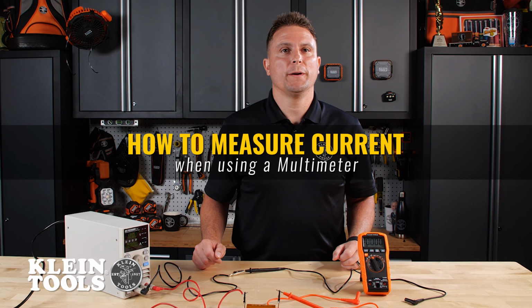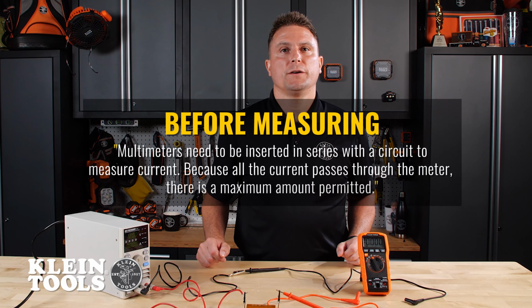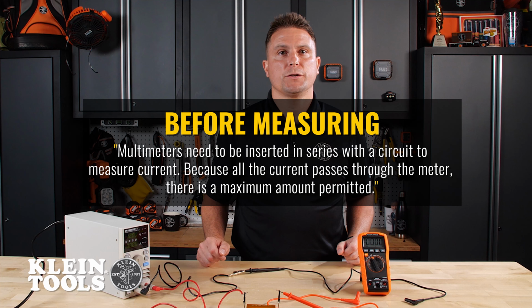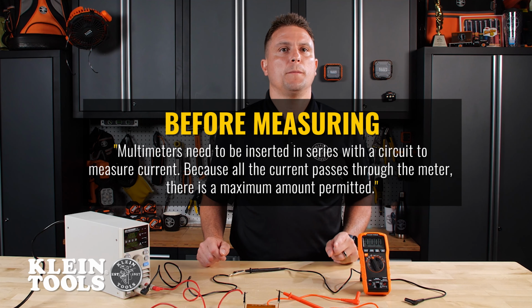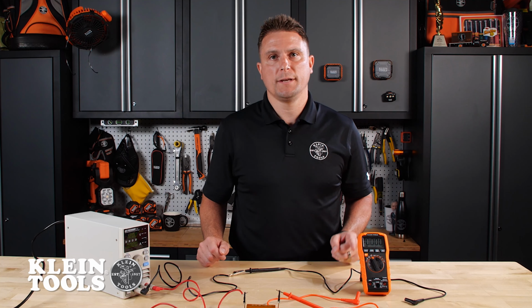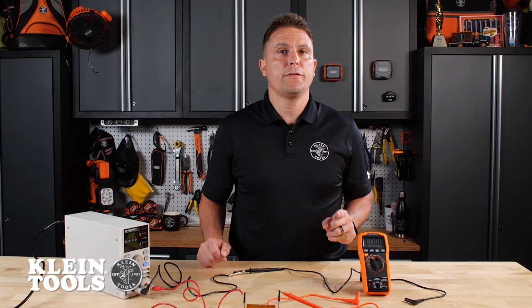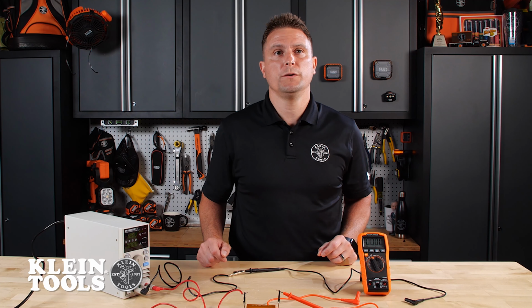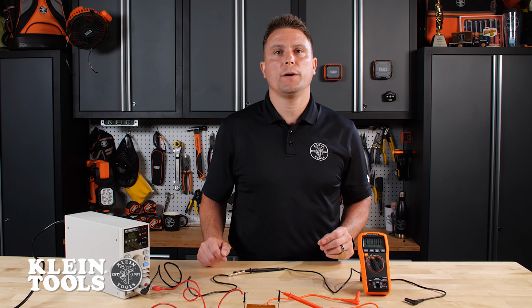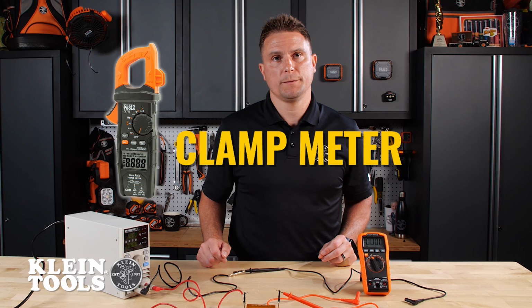Here's how to measure current. Multimeters need to be inserted in series with a circuit to measure current. Because all the current passes through the meter, there is a maximum amount permitted, 10 amps in this case. Currents higher than this value will blow the internal fuse. If you need to measure higher currents, consider using a clamp meter.